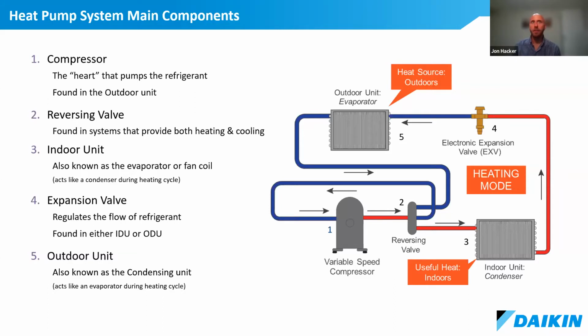And in addition to the inverter, the electronic expansion valve is a key component which enables a variable speed compressor to precisely modulate the amount of heating or cooling delivered. And they work together to regulate the flow of refrigerant based on the system operational parameters.